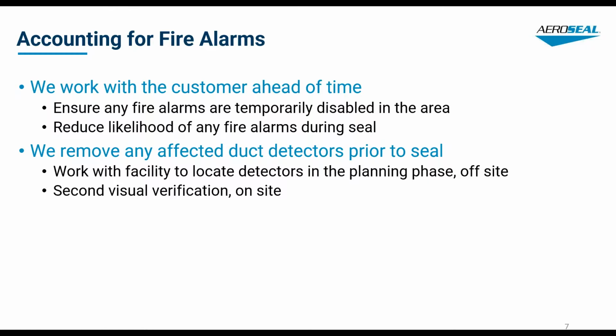As well as that, when we're in the facility looking at the ductwork to start sealing, we'll actually remove any duct detectors that we find, just as a double check. We don't want any accidents to happen if somebody forgets to turn off the fire alarm, which should never happen, but nobody's perfect. So we always take those out if we can find them. If we can't find them, we'll ask the customer representative on site if they know where the duct detectors are, and we'll take them out, bag them, and then once the sealing process is over, we'll replace them.